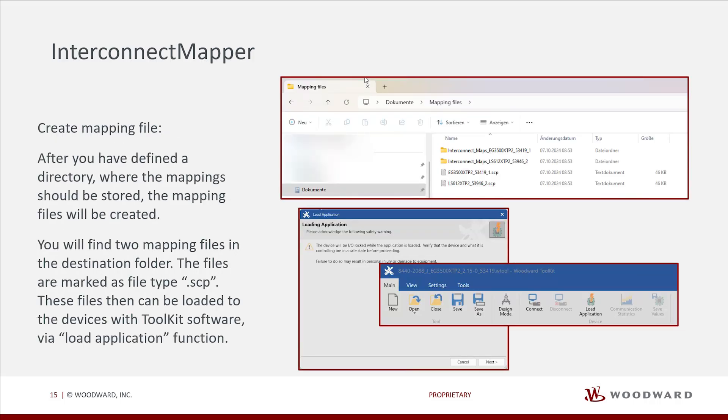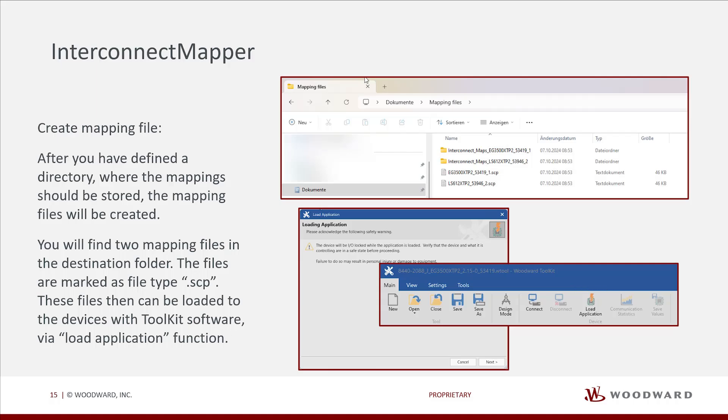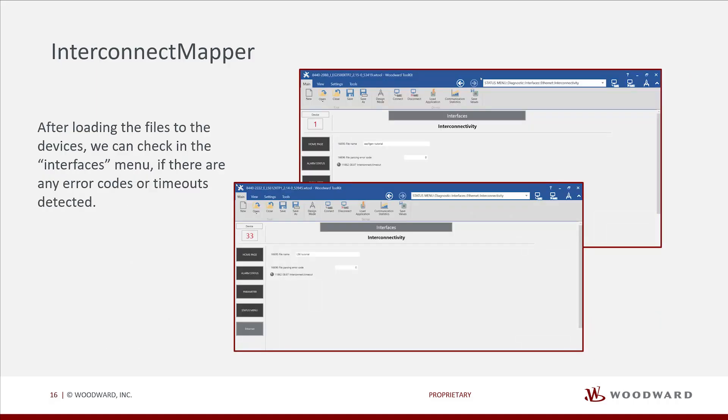After you have defined a directory where the mapping should be stored, the mapping files will be created. You will find two mapping files in the destination folder. The files are marked as file type SCP. These files can then be loaded to the devices with toolkit software via load application function. After loading the files to the devices, we can check in the interfaces menu if there are any error codes or timeouts detected.